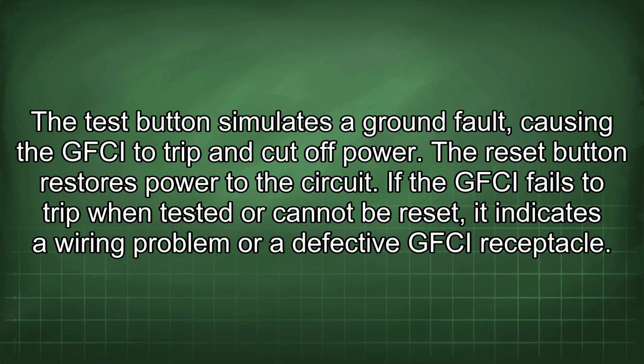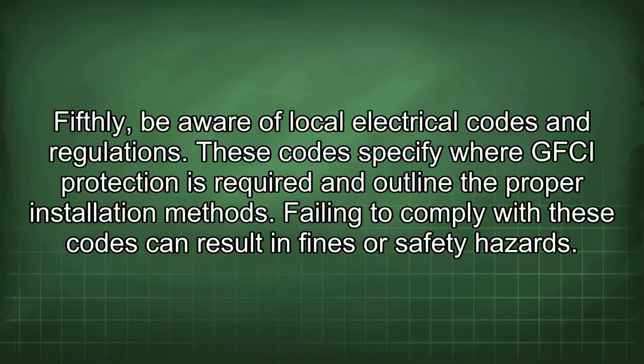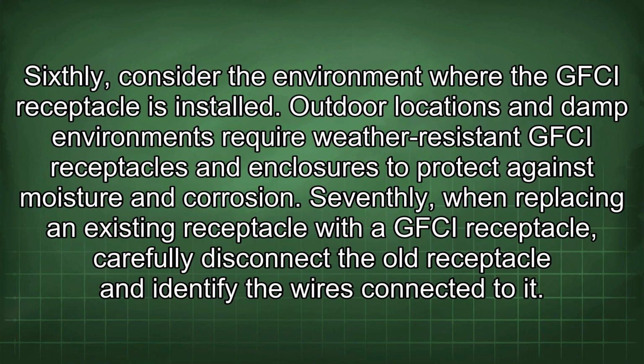If the GFCI fails to trip when tested or cannot be reset, it indicates a wiring problem or a defective GFCI receptacle. Fifthly, be aware of local electrical codes and regulations. These codes specify where GFCI protection is required and outline the proper installation methods. Failing to comply with these codes can result in fines or safety hazards. Sixthly, consider the environment where the GFCI receptacle is installed. Outdoor locations and damp environments require weather-resistant GFCI receptacles and enclosures to protect against moisture and corrosion.